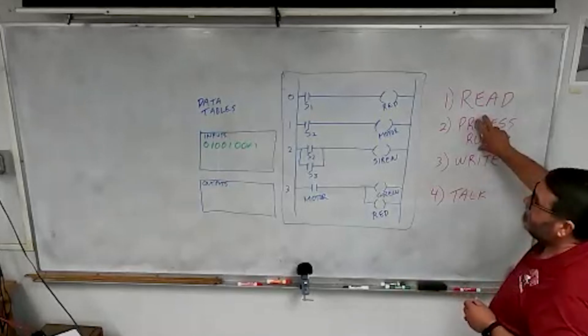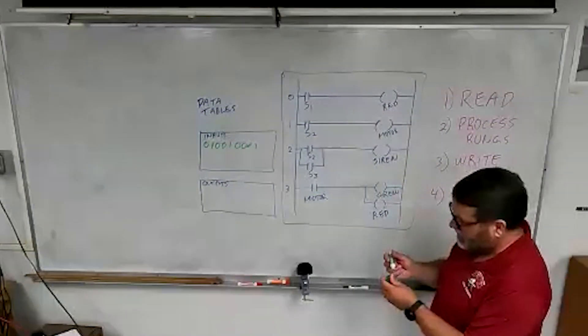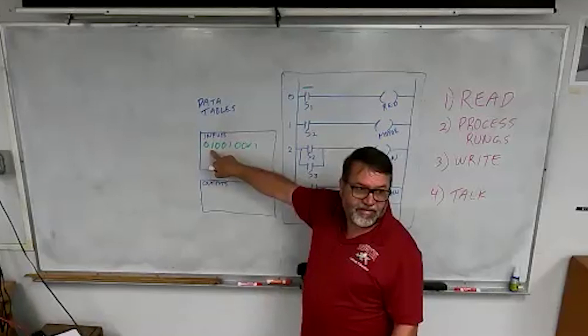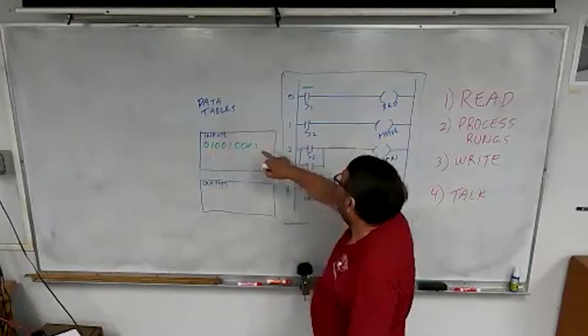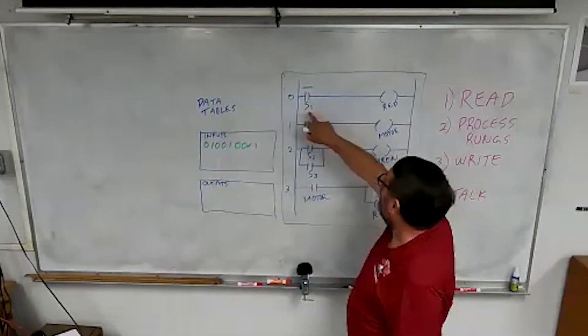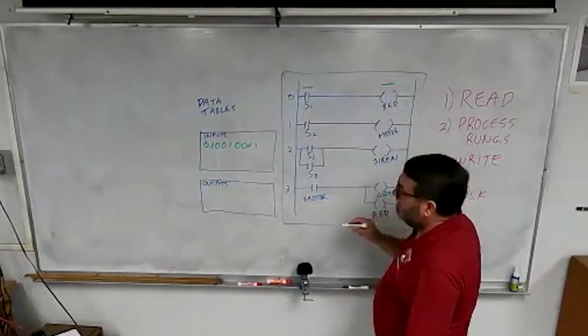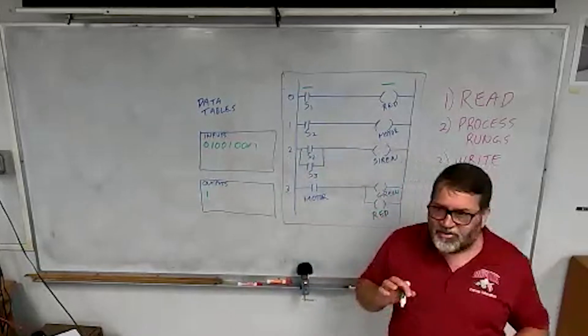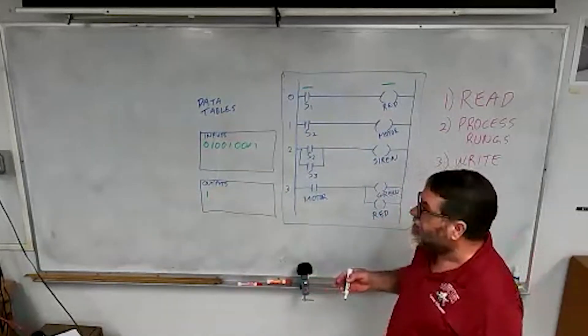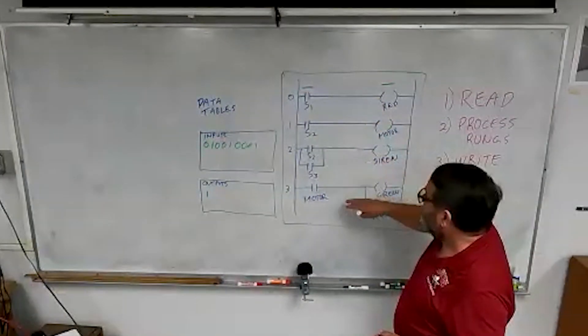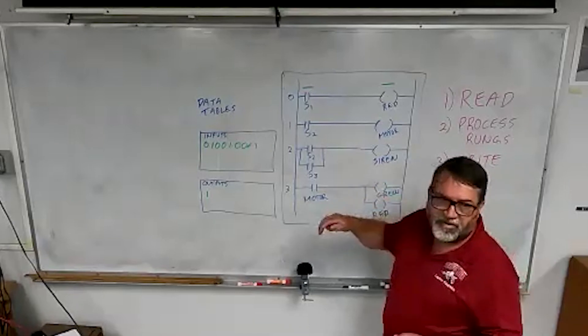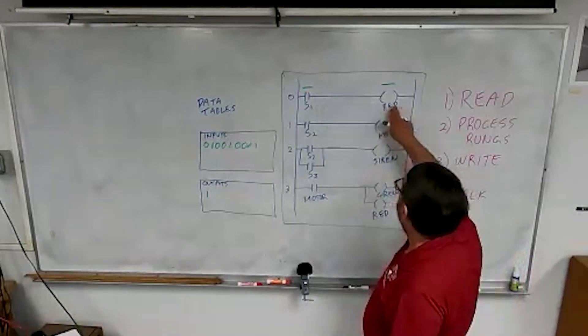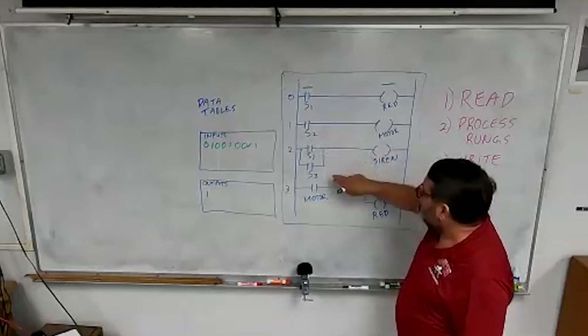The next step, they go and process all the rungs. And for example, if switch one is hot. So let's say that this address over here, this is switch one, and it's hot. So when it processes the rungs, it's going to say, okay, switch one is hot. And so I'm going to turn on a red light, and over an output, it's going to put a one to turn on a red light, but it doesn't actually turn that light on yet. It's just making a note that it has to turn it on. So it goes through all the rungs, and it figures out what it's going to do when it talks to the outputs. So switch one is hot. So the red is going to go hot, and the rest of these are all cold.